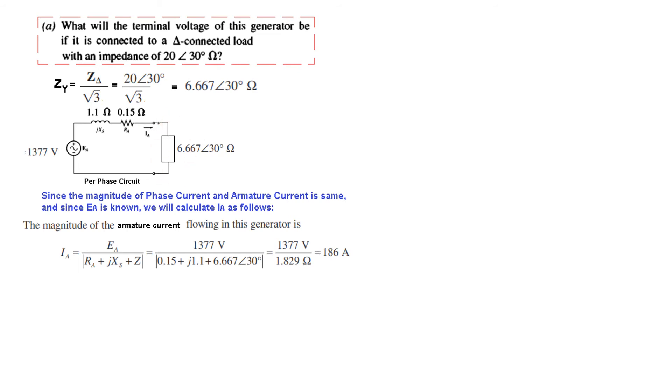Now we calculate the phase voltage. The phase voltage with load is I into Z, 186 into Z. The phase voltage is 1240 volts. To calculate the terminal voltage, we have to multiply the phase voltage by under root 3. So the terminal voltage with load is 2148V. This is the answer of the first part.